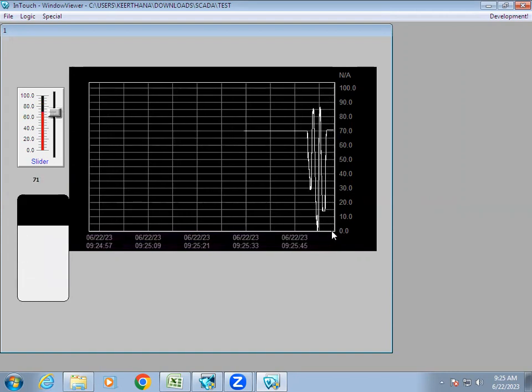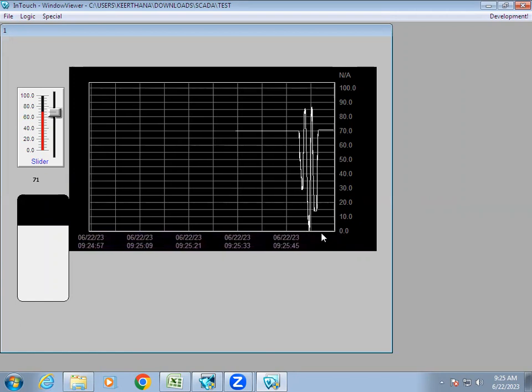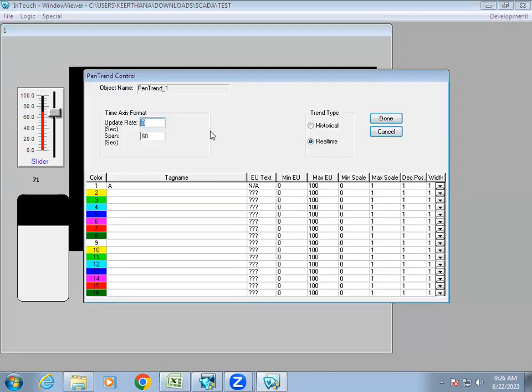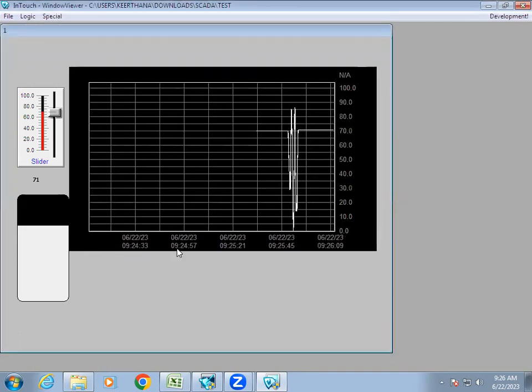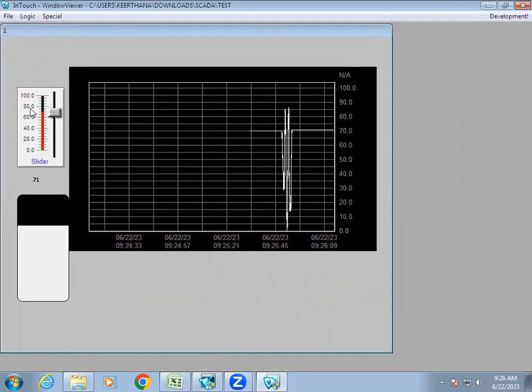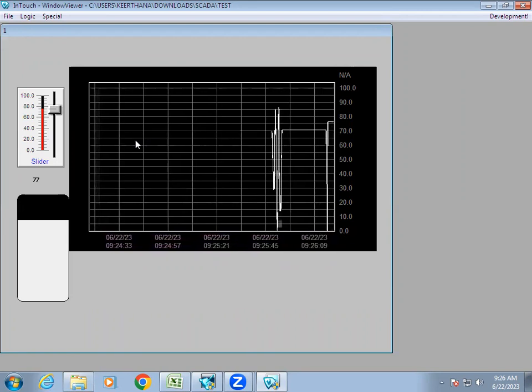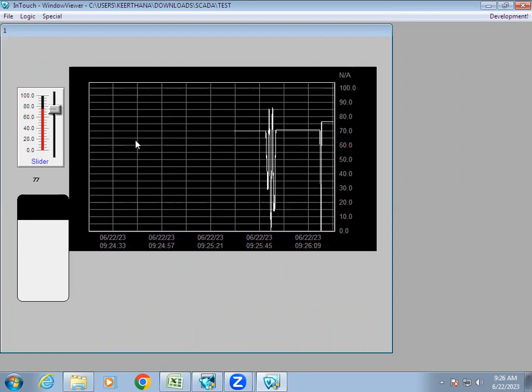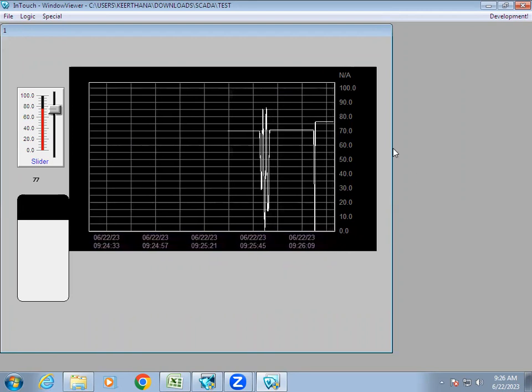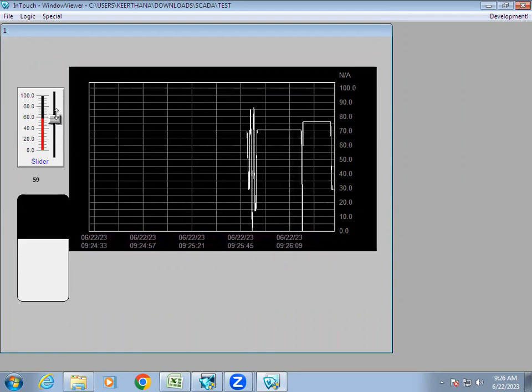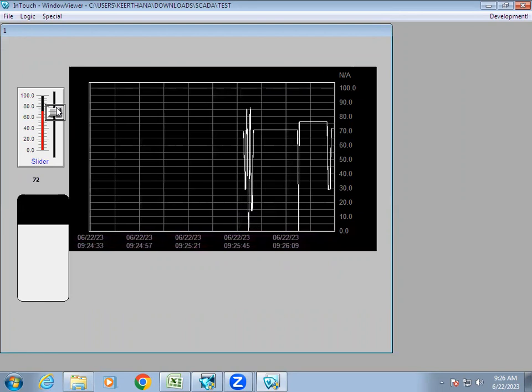Remember, the length of your chart on the X-axis is just 60 seconds by default. If you want to watch more than 60 seconds, you type the value here — for example, for two minutes you type 120, and the chart length becomes 120 seconds. However, if those two minutes have already passed and you want to see that past data, it is not possible in real-time trend. Real-time trend only shows current and present values.